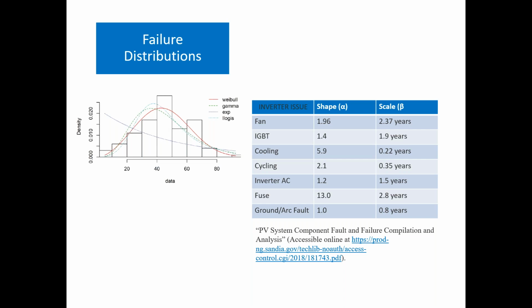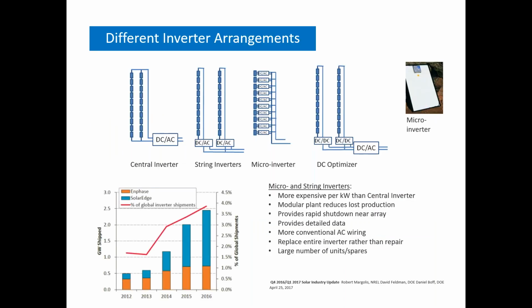If the beta is greater than 1, then it's an aging phenomenon, and the failure rate increases with time. So our failure rates are almost all of the type that Davide described as fatigue related, with failure rates that occur higher in the later years. But like I said, it depends on the type. So that discussion of replacing the components inside the inverter relates to a central inverter.